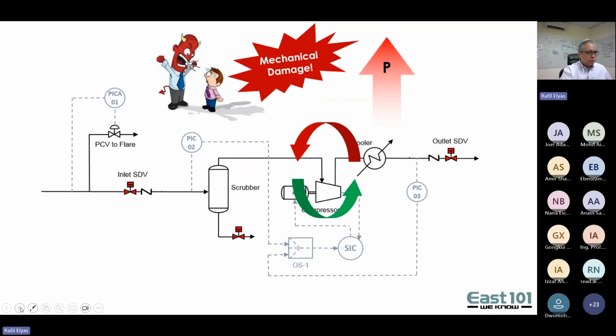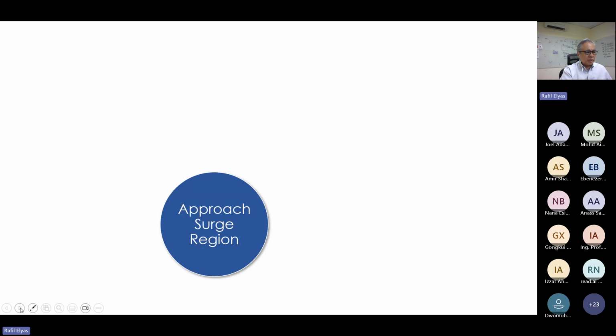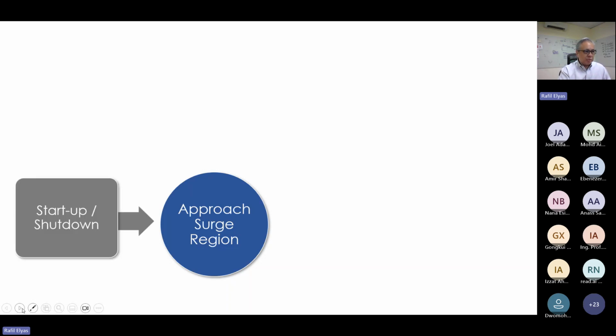So what do we do in a situation like this? Well, we need to take a look at certain types of analyses to see what sort of situations may bring a system to surge, where a compressor may start approaching surge. One might be startup or shutdown, particularly if you have an emergency shutdown and you cut the power to your compressor real quick.